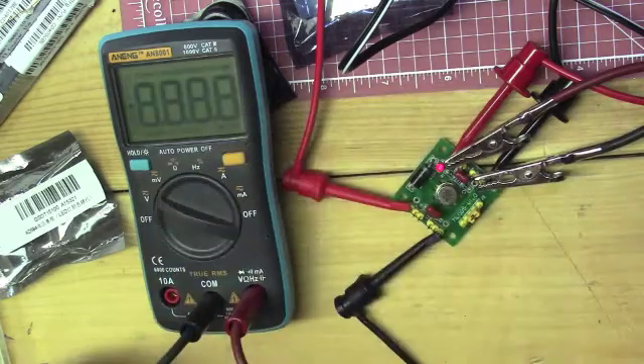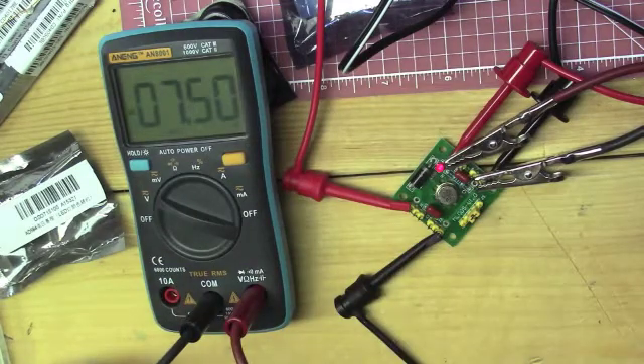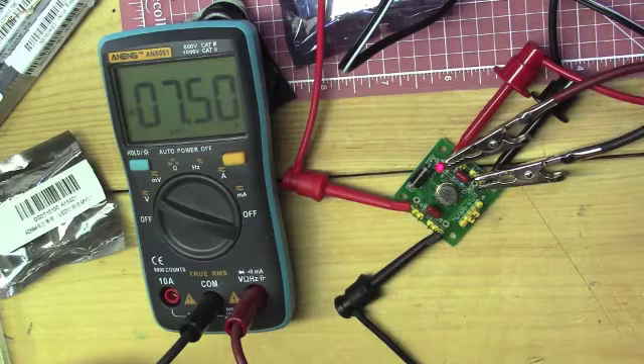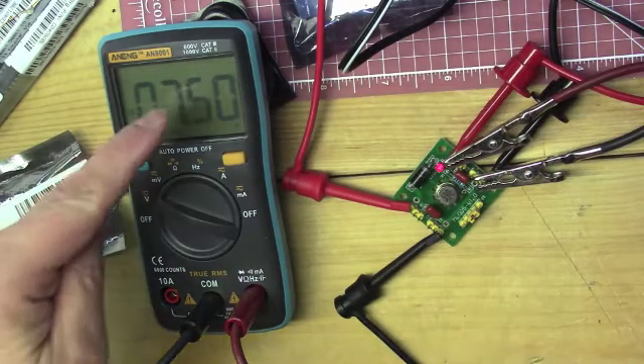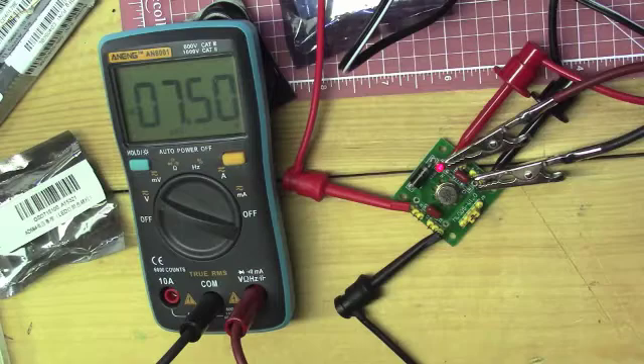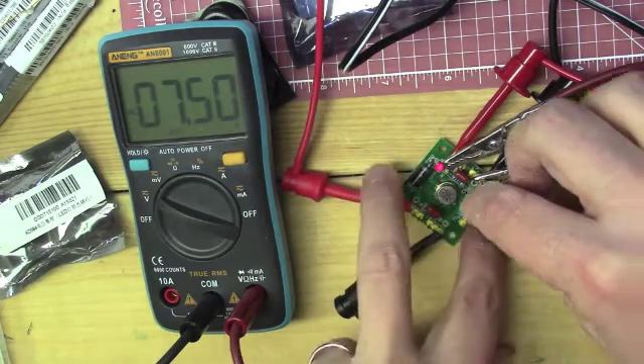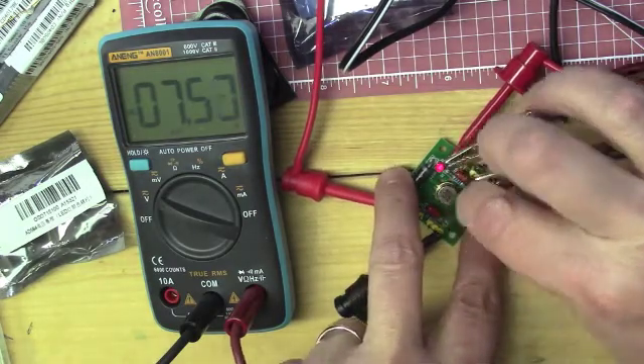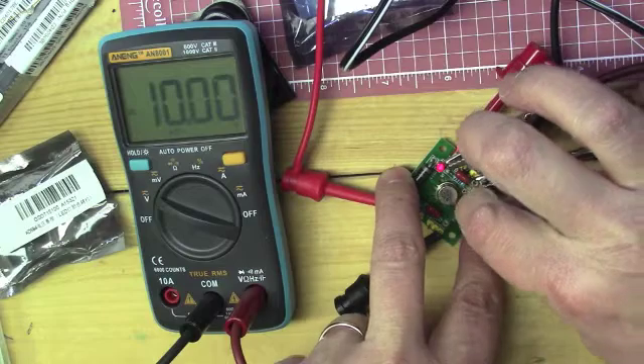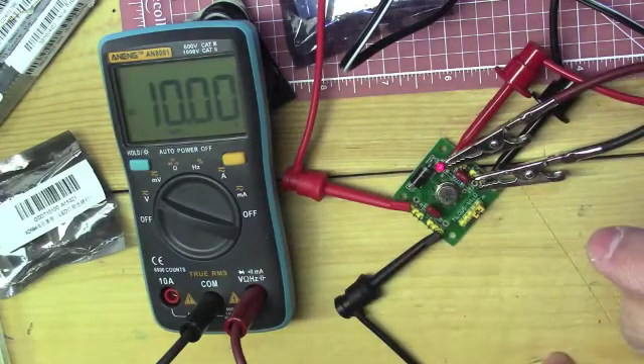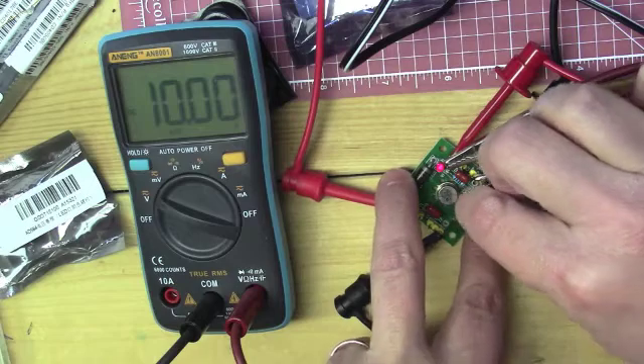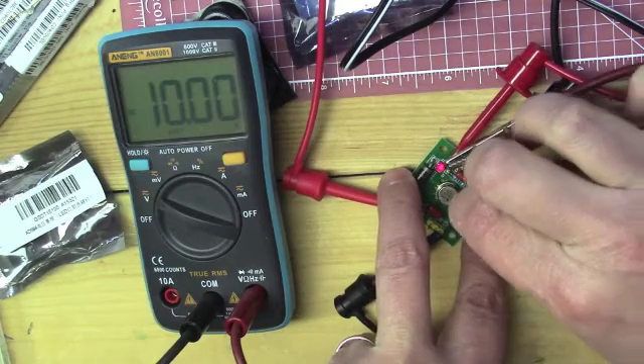So put it on the DC volts here and we have it on the 7.5 volt range right now, and as you can see right at 7.5 volts. So let me move the jumper, let's go back to the 10 volts first. I got 10 volts right on the money. We'll move it one more pin over, 7.5.